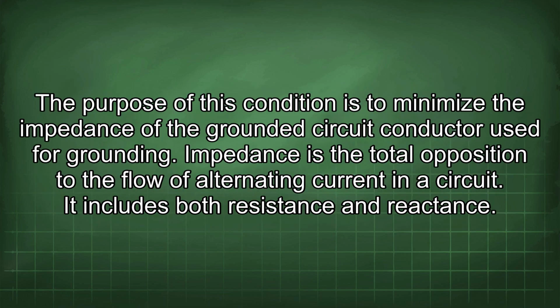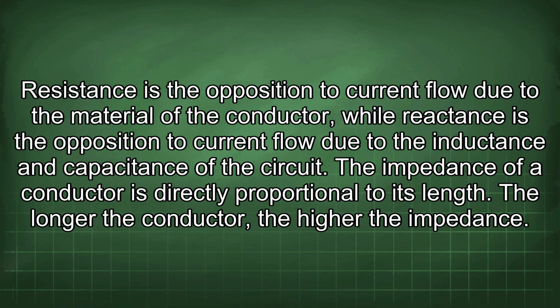The purpose of this condition is to minimize the impedance of the grounded circuit conductor used for grounding. Impedance is the total opposition to the flow of alternating current in a circuit. It includes both resistance and reactance. Resistance is the opposition to current flow due to the material of the conductor, while reactance is the opposition to current flow due to the inductance and capacitance of the circuit. The impedance of a conductor is directly proportional to its length. The longer the conductor, the higher the impedance.